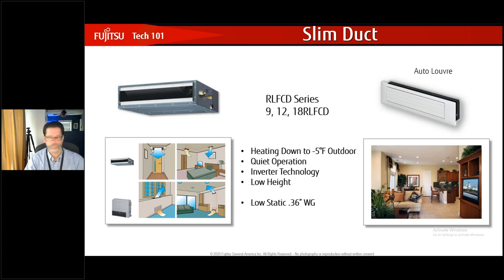It was a misapplication for that mini air handler, the low static. You cannot think you're going to overcome resistance of flex duct. You know, flex duct is nothing more than static builder. So smooth, rigid pipe ductwork, okay? Always better for airflow, regardless. Things seem more convenient, more budget-friendly, but they really start to hinder performance. And now when the complaint comes in, people want to point to the equipment, and it's not the equipment, okay? It's in a selection of the equipment. Yeah, I agree, the equipment's not getting it done, but it's not because of lack of performance. It is performing. It's doing exactly what it's supposed to do.